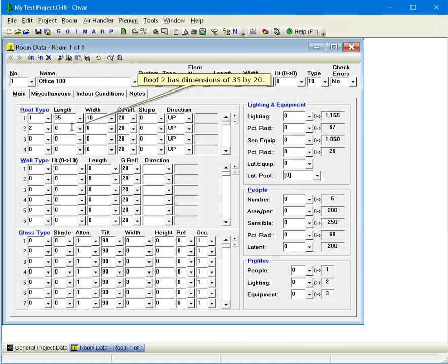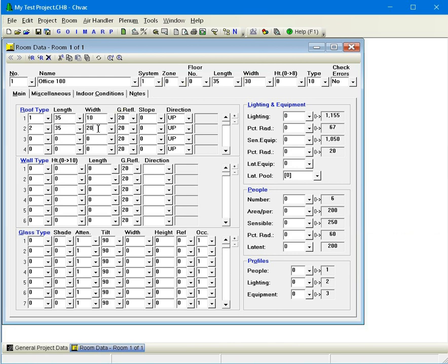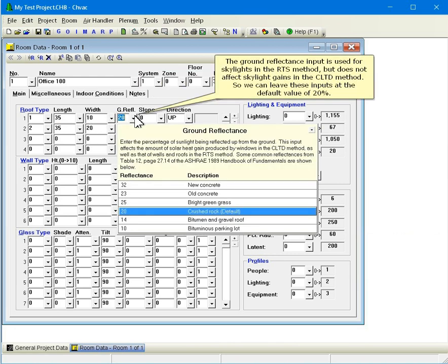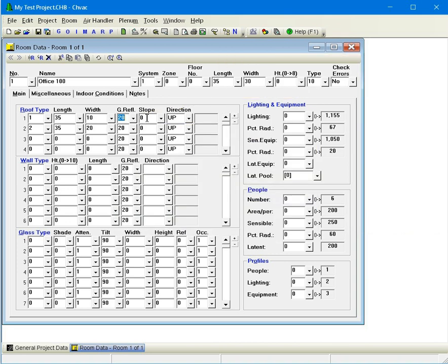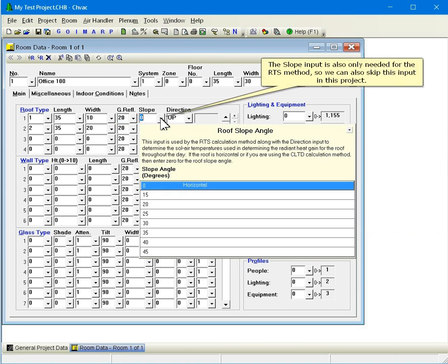Roof 2 has dimensions of 35 by 20. The ground reflectance input is used for skylights in the RTS method, but does not affect skylight gains in the CLTD method, so we can leave these inputs at the default value of 20%. The slope input is also only needed for the RTS method, so we can also skip this input in this project.